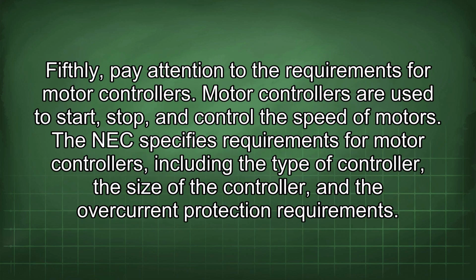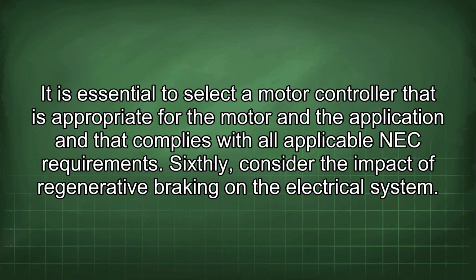Fifthly, pay attention to the requirements for motor controllers. Motor controllers are used to start, stop, and control the speed of motors. The NEC specifies requirements for motor controllers, including the type of controller, the size of the controller, and the overcurrent protection requirements. It is essential to select a motor controller that is appropriate for the motor and the application and that complies with all applicable NEC requirements.